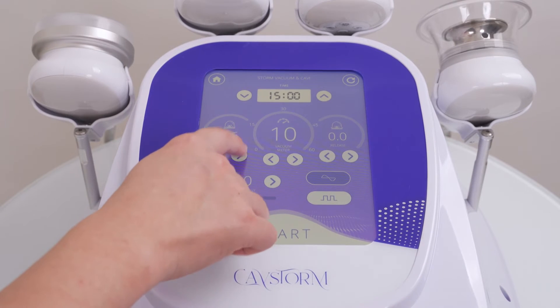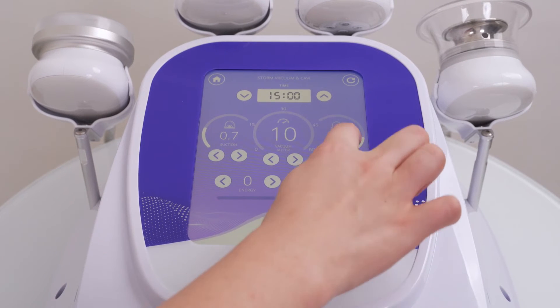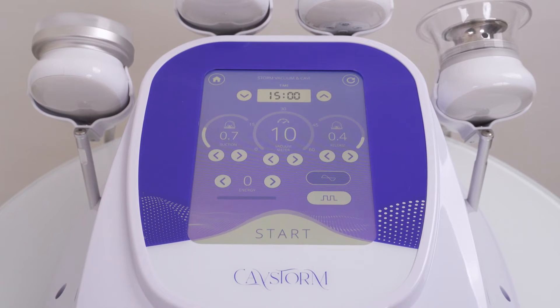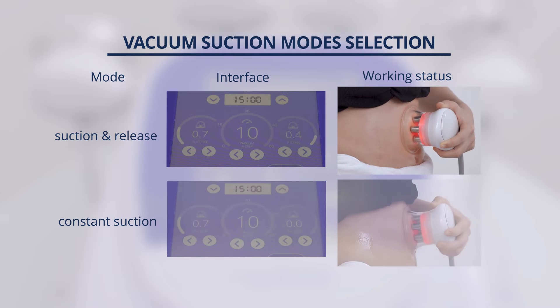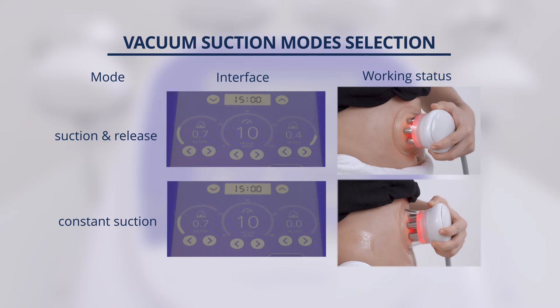For vacuum, suction time range and release time range are 0 to 2, both freely adjustable. When release time is not 0 and suction time is longer than release time, the handpiece is in suction and release mode. When release time is 0, the handpiece is in constant suction mode.